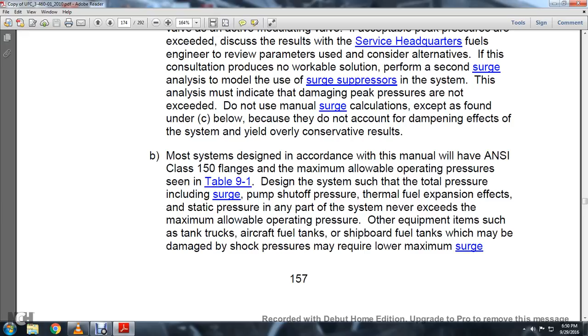Do not use manual calculation instead of computer modeling when the system surge pressure is crucial or the piping system is complex. However, for a simple piping system that operates under 80 psi, the manual calculations contained in Appendix B can be used to assess if surge will be a problem.